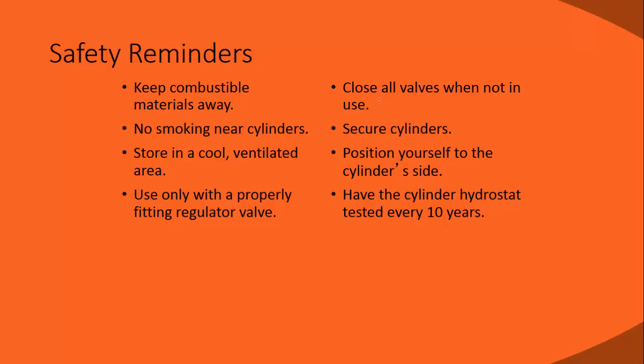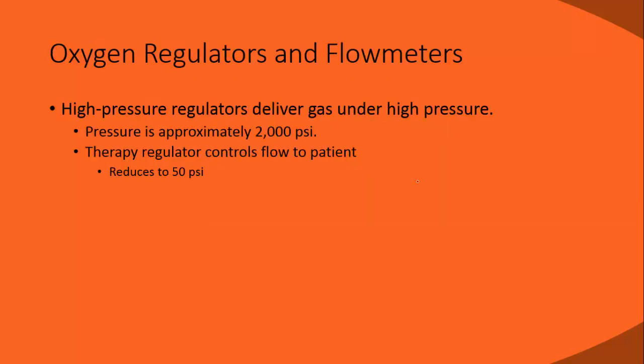Some other ideas: we want to make sure that we're closing the valves when not in use. It's a couple things. One is these oxygen tanks get moved around a lot, and so if the valve is open, it's going to leak. The other thing is if the valves are open, they can accumulate some dirt, and that would be a problem if we start providing oxygen to our patient with a nasal cannula. Cylinders should always be secured wherever they're present, and you should never put the cylinder in direct line against you, so pointing at you. You want yourself on the side in case it breaks, all right, because then it becomes obviously a projectile.